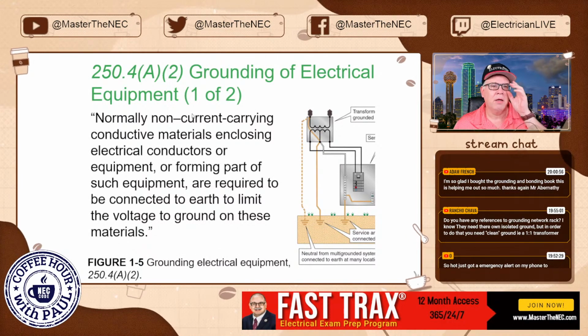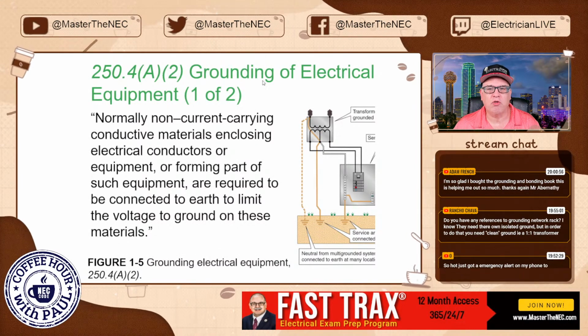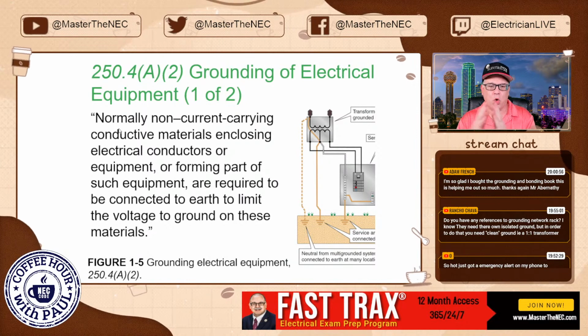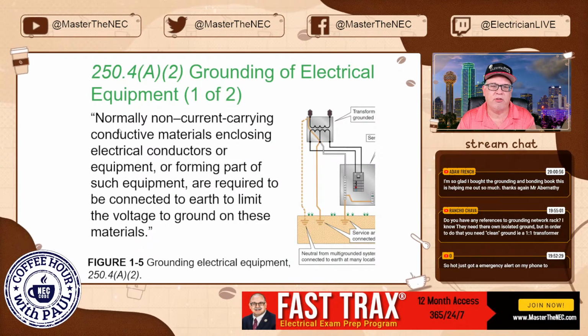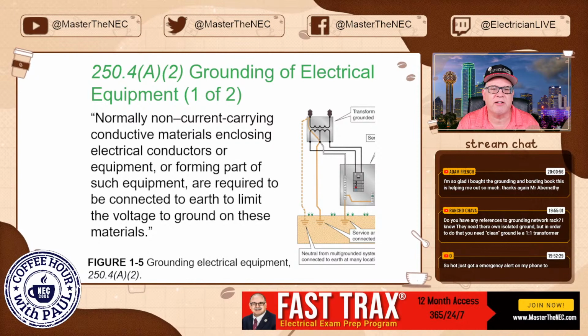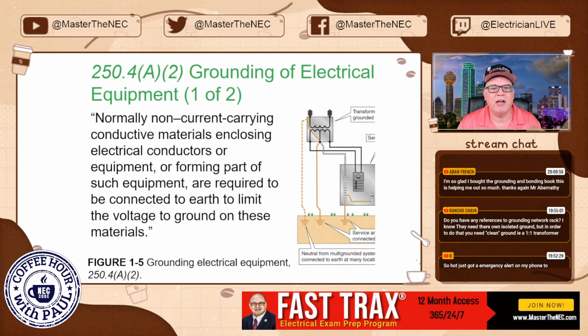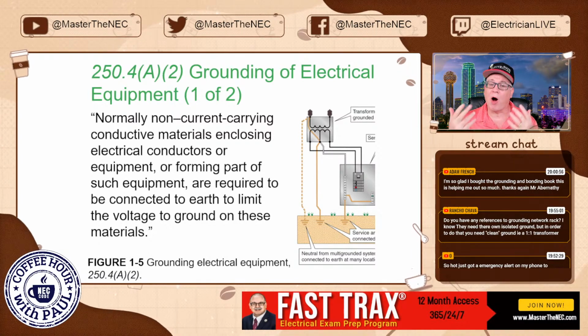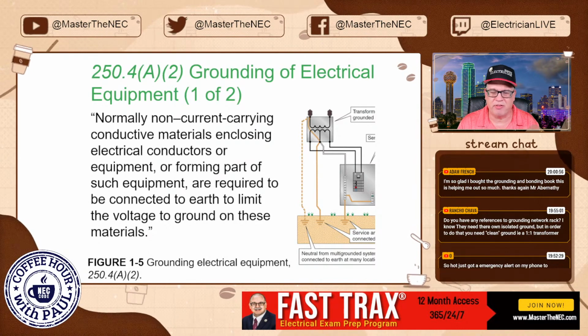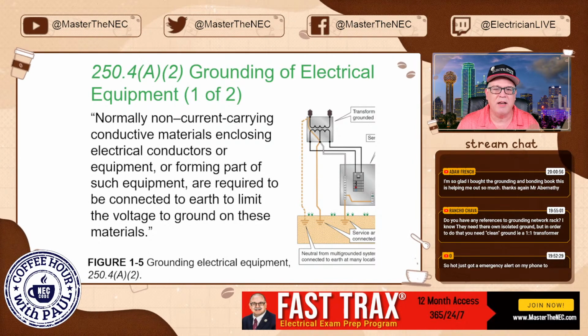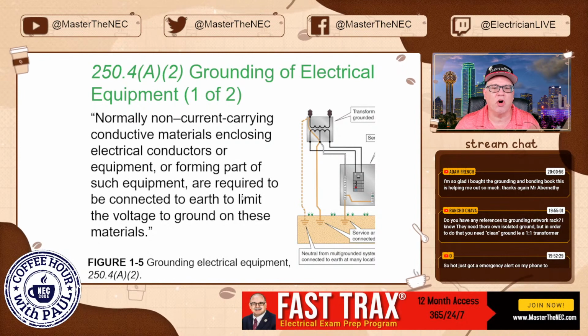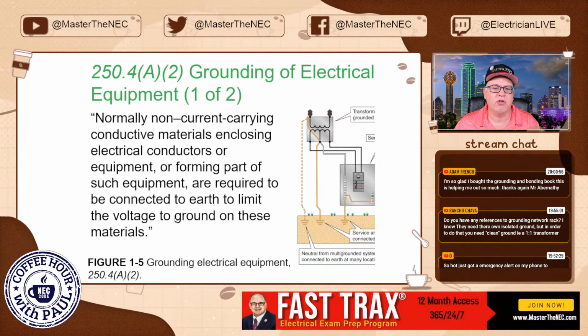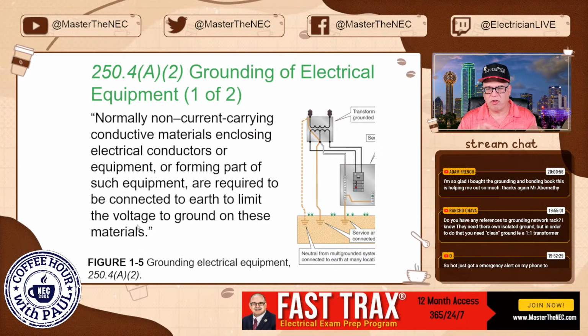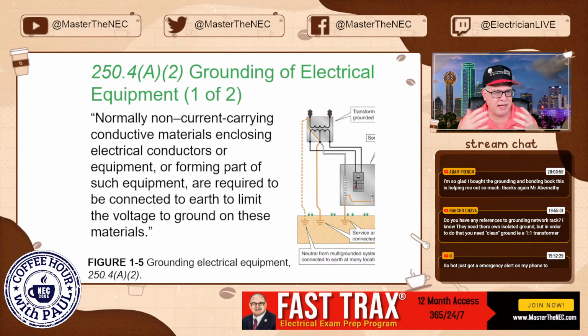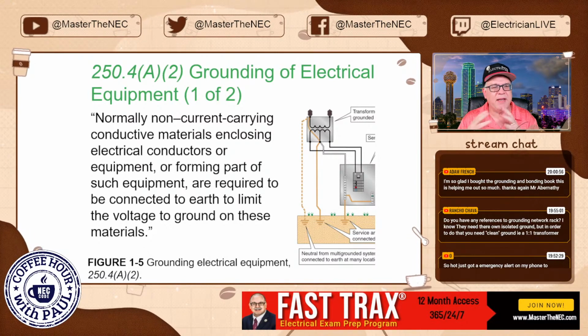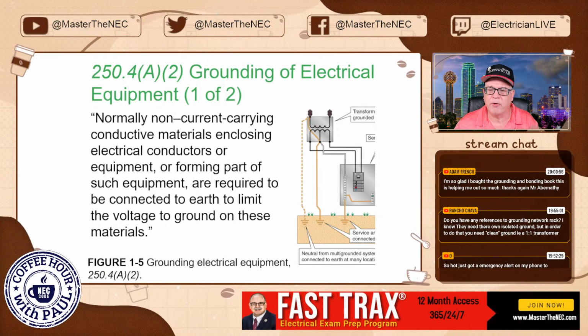All right. So 250.4(A)(2), grounding of electrical equipment. Quote from the code, 250.4(A)(2), it says, normally non-current-carrying conductive materials enclosing electrical conductors or equipment, or forming part of such equipment, that would be like the cabinets, the enclosures, the raceways, all of that, are required to be connected to earth to limit the voltage to ground on these materials. So bonding, tying all metal parts together.